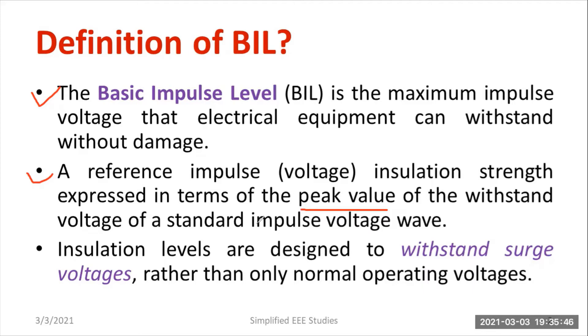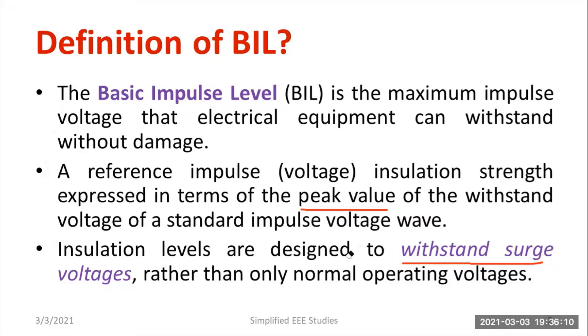Puncture occurs for solid dielectric material, and flashover for liquid and gaseous type dielectric material. That will take place if the particular level fails to be maintained. Additionally, insulation levels are designed to withstand surge voltages rather than only the normal operating voltage. This is the importance of BIL.